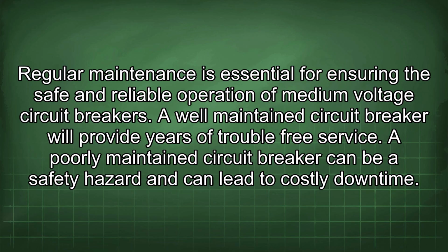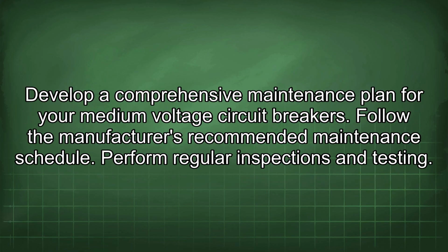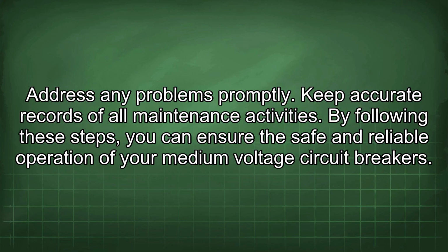Regular maintenance is essential for ensuring the safe and reliable operation of medium voltage circuit breakers. A well-maintained circuit breaker will provide years of trouble-free service. A poorly maintained circuit breaker can be a safety hazard and can lead to costly downtime. Develop a comprehensive maintenance plan for your medium voltage circuit breakers. Follow the manufacturer's recommended maintenance schedule. Perform regular inspections and testing. Address any problems promptly.